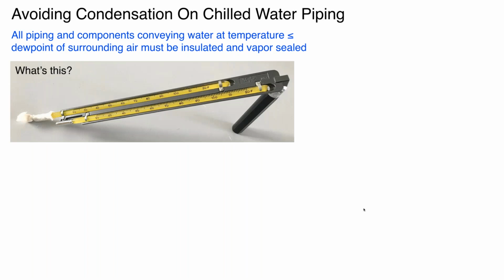So I always like to put this device up and ask what it is. I'm sure some of you have seen these things. Maybe you played with one in an HVAC lab years ago. This is called a sling psychrometer. You'll see there are two mercury thermometers in that main block, and then there's a handle over on the right. One of the thermometers has a wick on the bulb. The way you work this is you saturate that wick with water, then you grab the handle and literally spin the thing around for about 30 seconds. As you do that, the water is evaporating from the wick. After about 30 seconds, you read both thermometers.